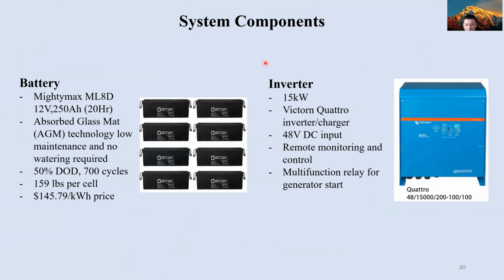Now move on to why we choose these system components in our system. Let's start with the battery. The battery we choose is a Mighty Max battery having the capacity of 12 volt 250 ampere hour for 20 hours. This battery is maintenance free, so there is no need of watering. It can go up to 700 cycles for 50% depth of discharge, which will last at least 2 years.